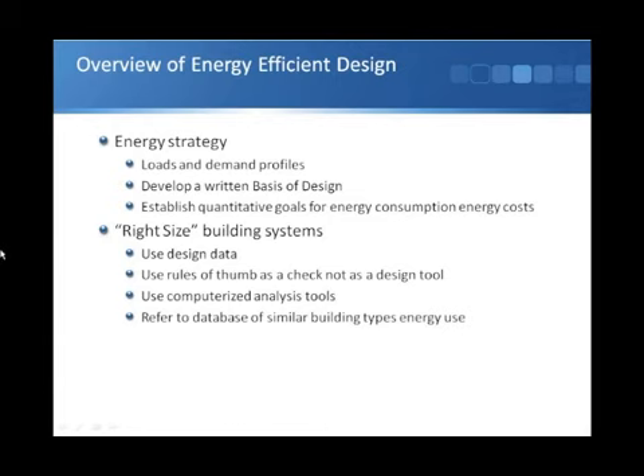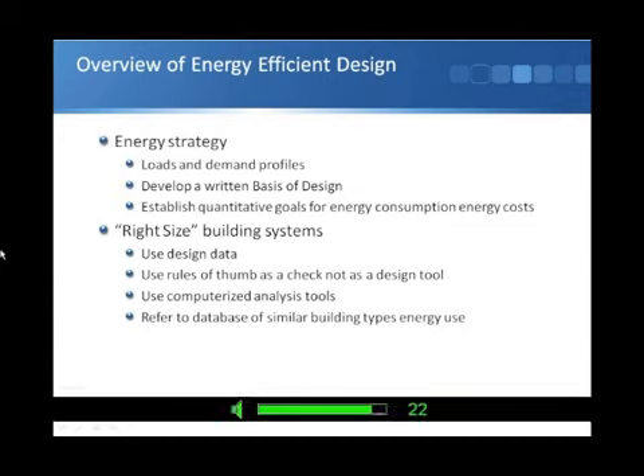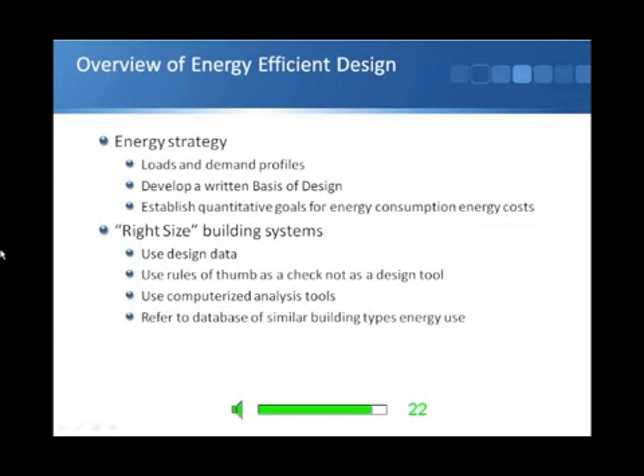I'd encourage us to use good design data, CIBSE guides in the UK, ASHRAE guides, of course. Not really using rules of thumb as design data. Rules of thumb are there as a check, as a back check, to make sure we're in the right area. They're not a method of sizing plants. So the old idea that we size heating systems on 100 watts a square metre or 50 watts a square metre, that's not the way to do it.